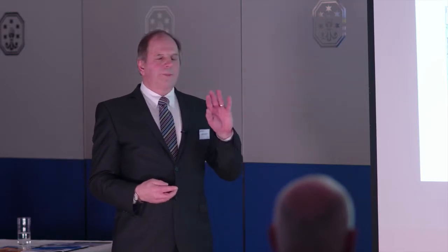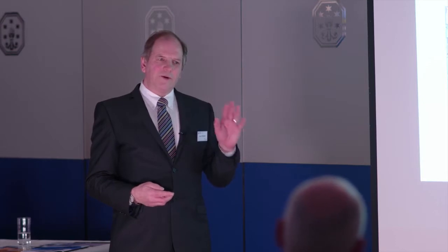The rapid decon hatch looks like that, and that is based on a 30-minute cycle time. Integrated catalyst, fast and effective distribution, really high turbulence in there to get movement through the loads, point contact presentations, all the things we've learned and all the science that you can have. You can get these rapid cycles if you do the right things. It's just science.